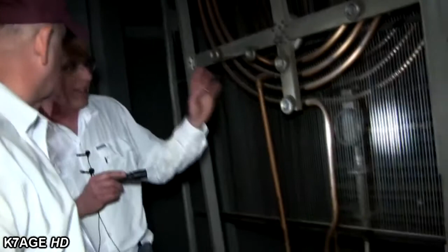So this is the part of the building that was added on when the 500 kilowatt transmitter was built, and there's again remnants of the 500 down here. When the 500 was built, there was a substation built out on Tylersville Road. Right now there's nothing left but the weatherheads where the cables come out of the ground. But there were huge transformers, disconnect circuit breakers, and two feeds - one came from the Port Union substation, the other came from the Oakley substation - and they could select power from either of the two substations feeding into the plant.